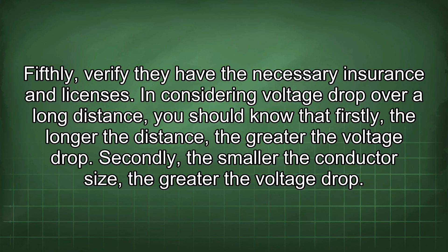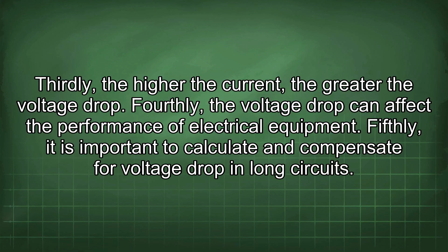In considering voltage drop over a long distance, you should know that firstly, the longer the distance, the greater the voltage drop. Secondly, the smaller the conductor size, the greater the voltage drop. Thirdly, the higher the current, the greater the voltage drop. Fourthly, voltage drop can affect the performance of electrical equipment. Fifthly, it is important to calculate and compensate for voltage drop in long circuits.